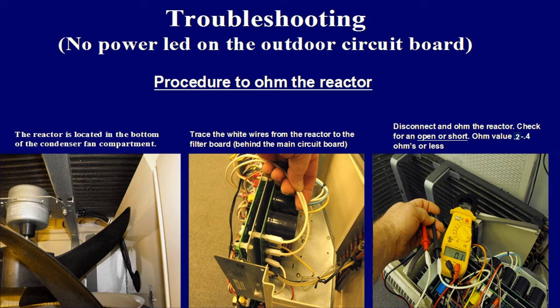If the reading is open, also check the electrical spade connections on the reactor itself to verify no corrosion has obscured this connection. If the wiring connections are good, then replace the reactor.